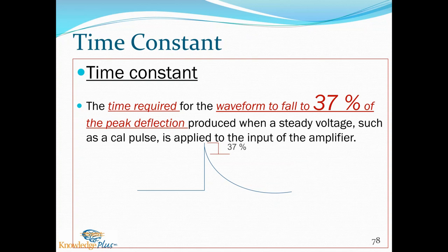Now, there are two different settings that control or influence low frequency activity. One is the low frequency filter, and the other is time constant. Time constant is defined as the time required for a waveform to fall to 37% of the peak deflection produced when a steady voltage, such as a calibration pulse, is applied to the input of the amplifier. So on your test, if you see the number 37%, they're talking about time constant.